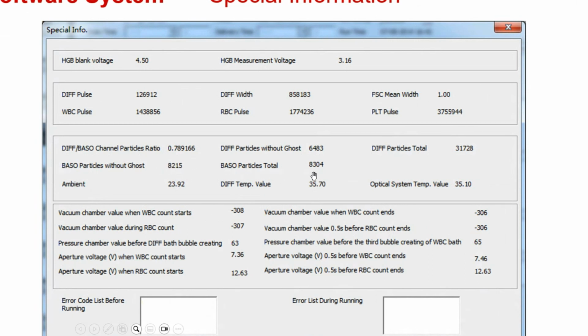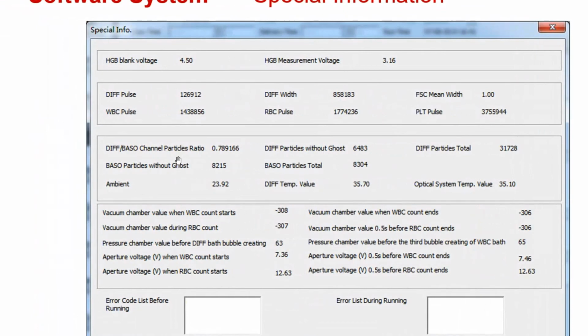And this is the baso particle total. It means all the particles that generated some impedance passing through the aperture. It is 8,300. So between the WBCs without ghost, the WBCs in the impedance channel and the WBCs in the diff channel should be close to each other. Normally, when I take this one and divide it by this one, I should get something close to 0.9. Okay, this is the good one.